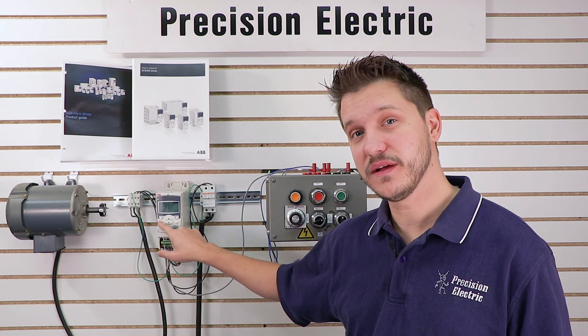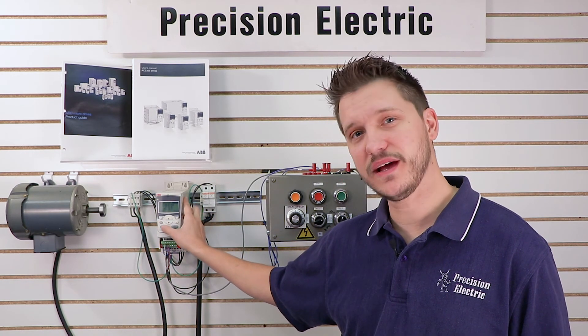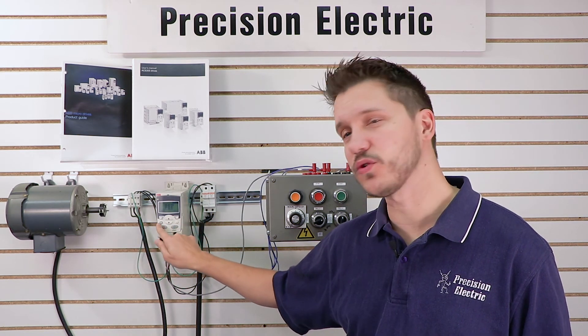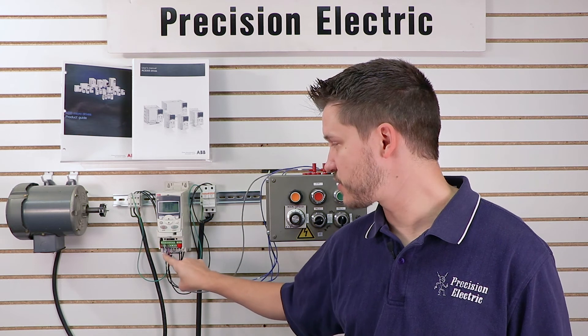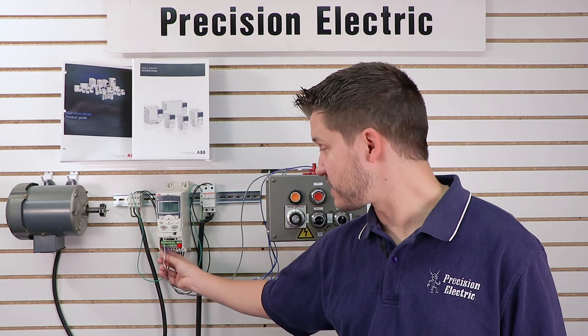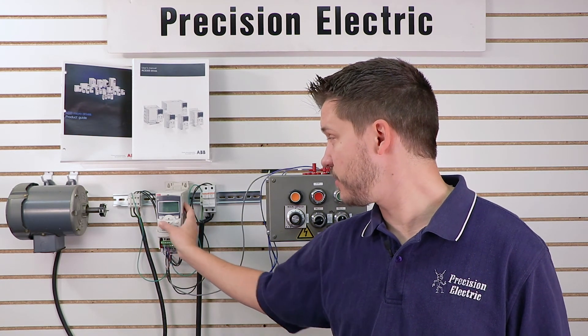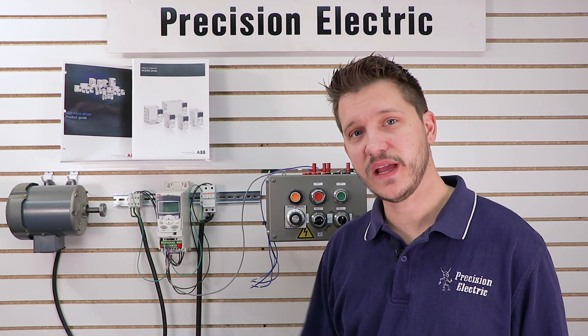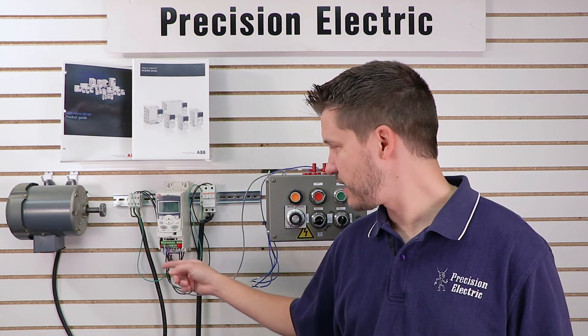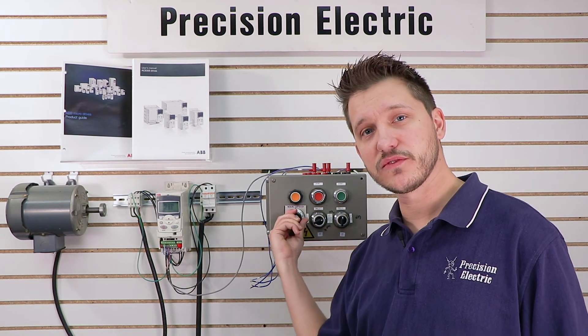Essentially all I need to do is to switch from my keypad control, which I can start right now from the keypad and stop from the keypad, is I press this local remote button and it'll actually switch over to the terminal strip. And it's going to start right away, and the reason I bring that up is because remember I jumpered my start command. So let me go ahead and switch to remote, and as soon as I switch to remote it receives that start command from my jumper, and now it's looking at my speed pot for speed.